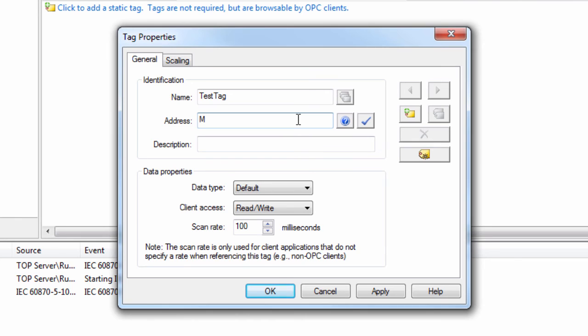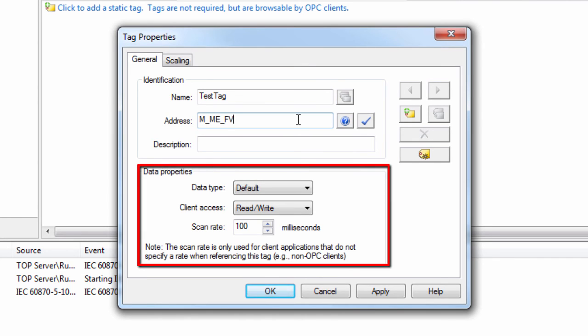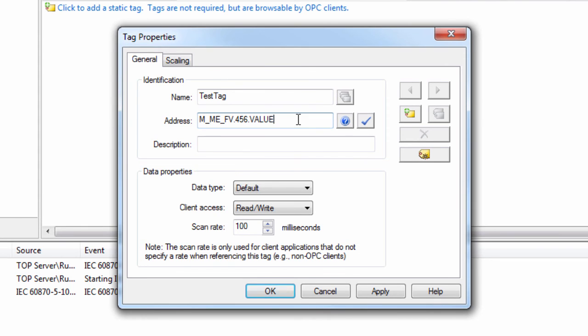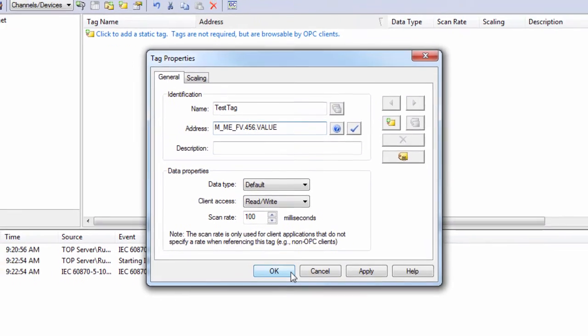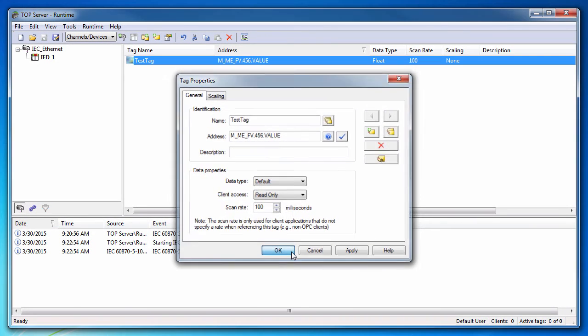The data type and client access can be set in the Data Properties window. Due to OPC specifications, the Tag Scan Rate setting is only applicable for non-OPC clients that do not abide by a group update rate in the client. Click OK and you will see your newly created tag in the project.